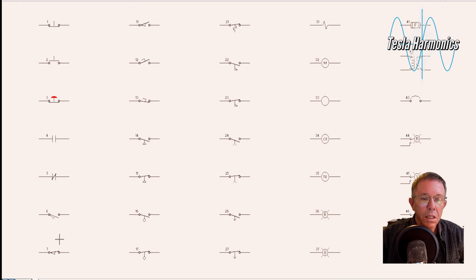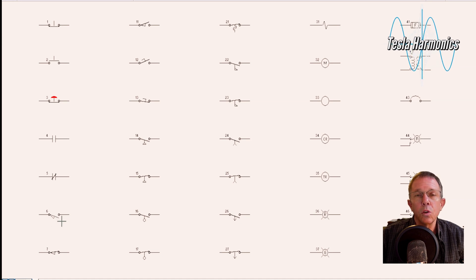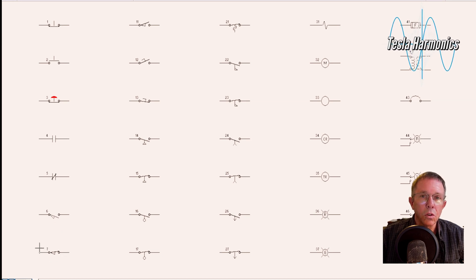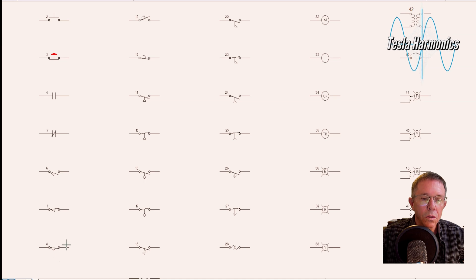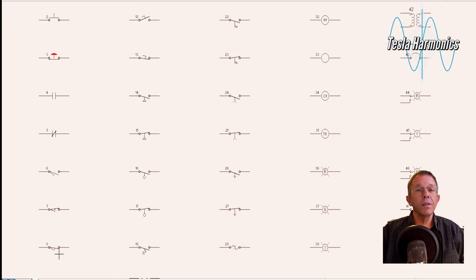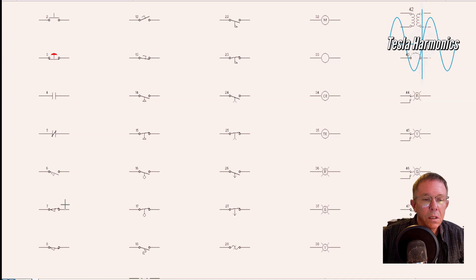Then we have a normally open limit switch, and then a normally closed limit switch. When looking at limit switches, I want to distinguish where the operator is in its normal position. If it is hanging below the circle on the right, that is a normally open limit switch. If it is sitting on top of the circle on the right, that is a normally closed limit switch. Number 8 is a normally open, held closed limit switch — that means it started off as normally open but something is holding it in place.